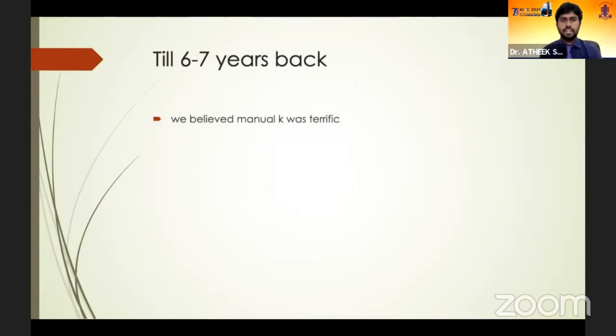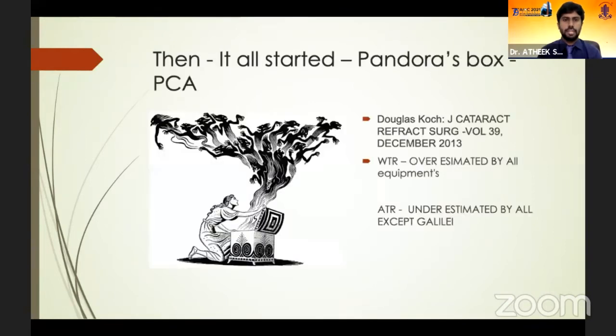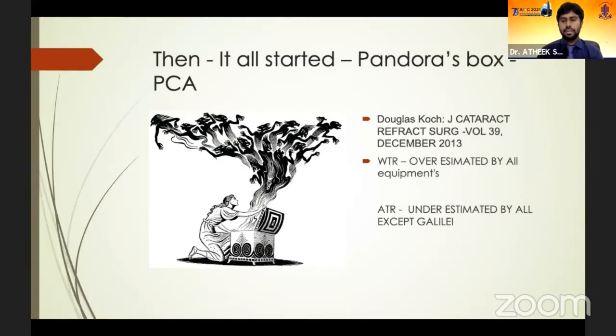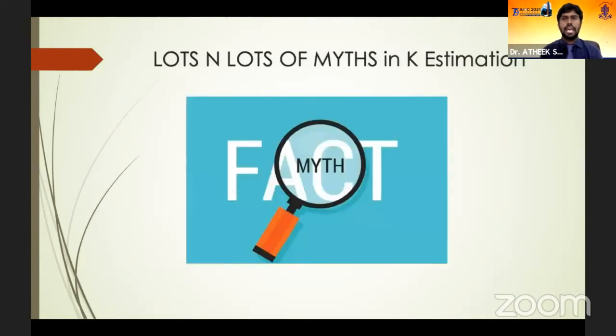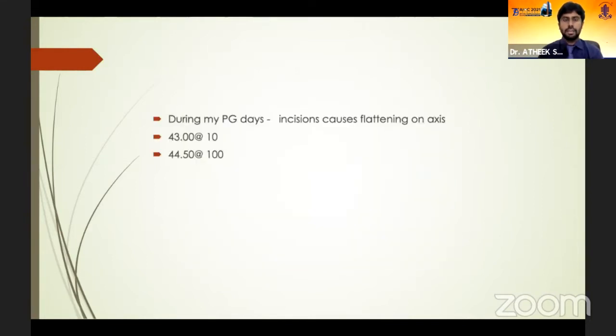Until about six to seven years ago, we believed manual K was an absolutely terrific instrument. Then came the landmark trial by Dr. Douglas Koch, who estimated posterior corneal astigmatism and found it to be significant. This opened a whole new endeavor in keratometry and astigmatism management in cataract surgery. The study found that manual K, second-generation optical biometers, and auto K all give wrong values. Even Pentacam was overestimating with-the-rule astigmatisms, except the Galilei.